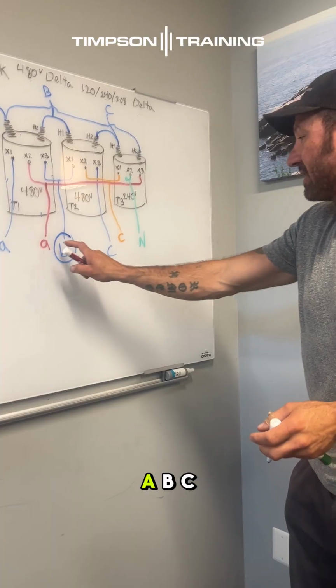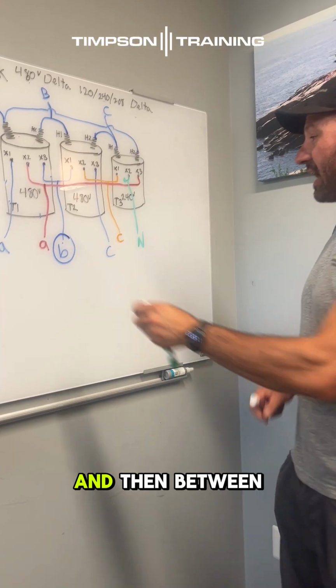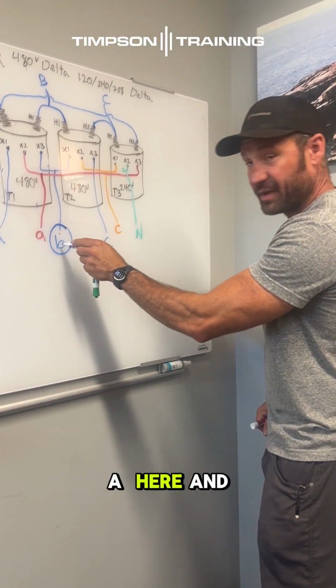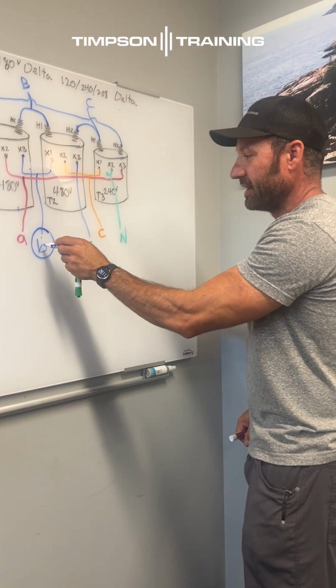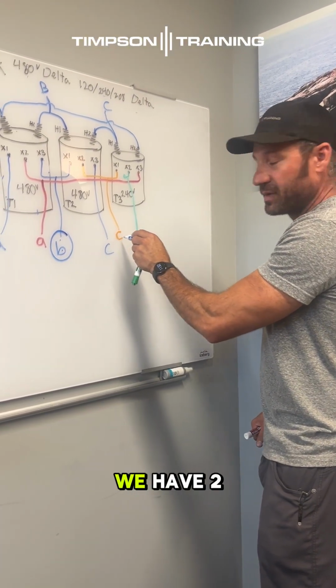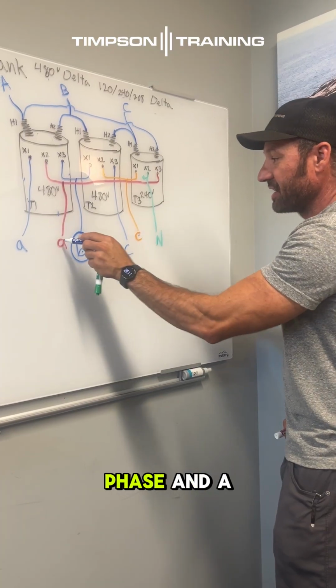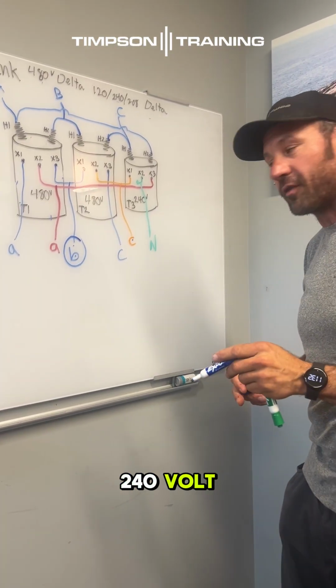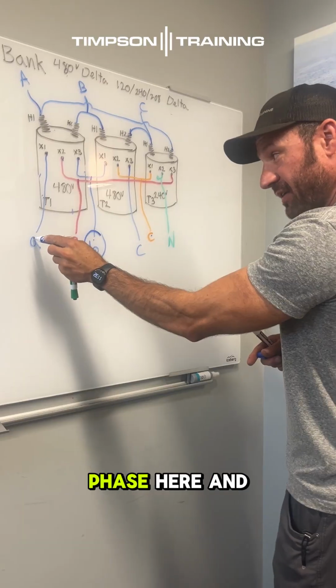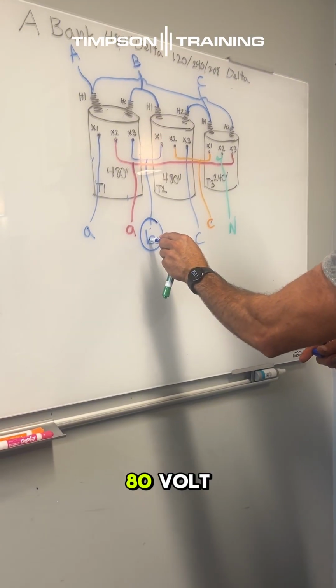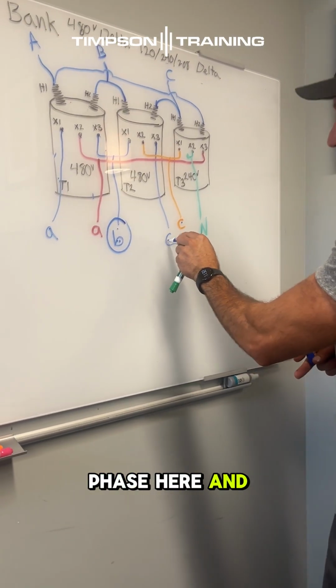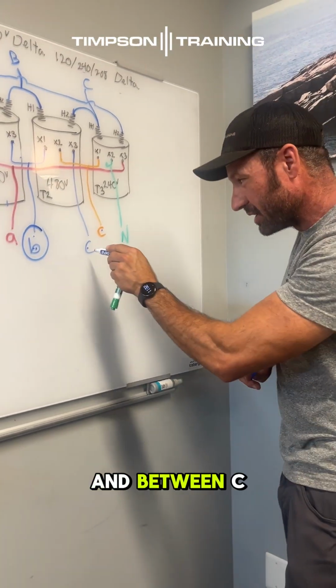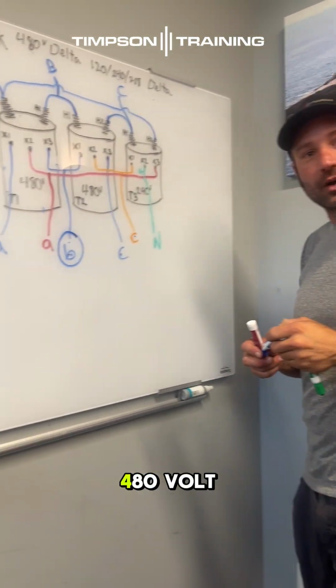So we have A, B, C, and then between A here and B phase, we have 240 volt. Between B phase and C phase, we have 240 volt, and between C phase and A phase, we have 240 volt. But between A phase here and B phase, we have 480 volt. And between B phase here and C phase here, we have 480 volt. And between C phase and A phase, we have 480 volt.